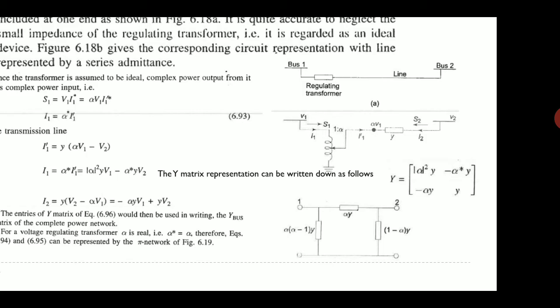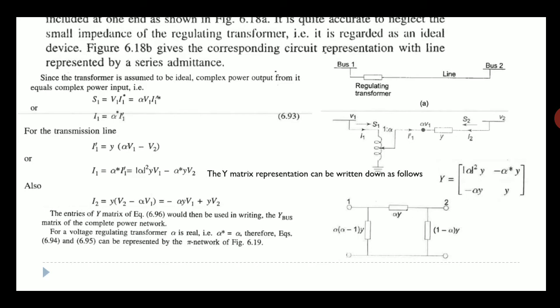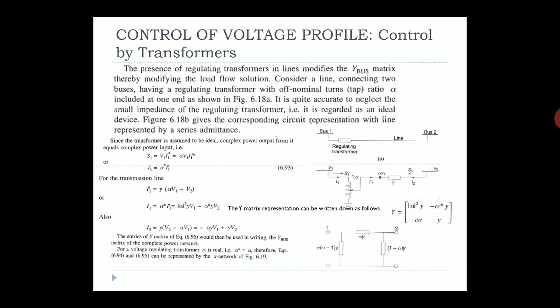The Y-bus matrix for this two-bus section can be represented as: [|α|²·y, −α*·y; −α·y, y]. This matrix must be included in the overall Y-bus matrix. When a regulating transformer with tap ratio alpha is present, the Y-bus values change accordingly and must be updated before computing the load flow solution. This is how the regulating transformer is incorporated into the load flow analysis.